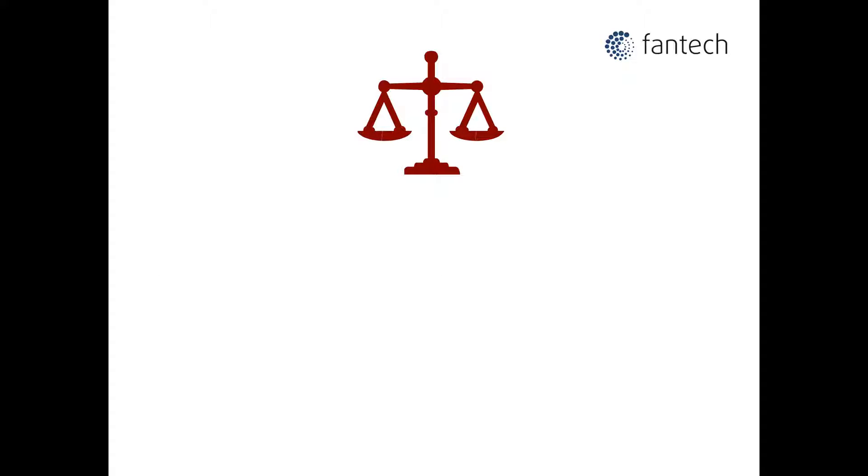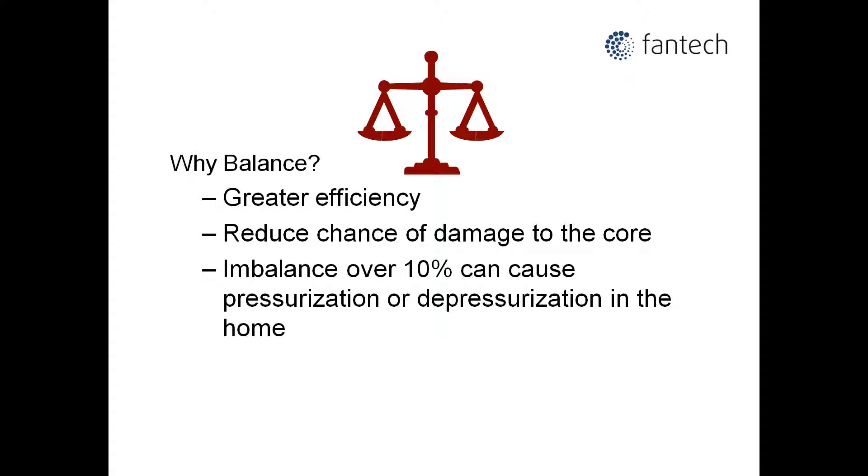A HRV or ERV works best and is most efficient when the air flows are equal. In areas where freezing occurs, a balanced system stands less chance of freezing up. Also it does not depressurize the home causing backdrafting of fossil fuel appliances or open fires, or pressurizing the home forcing moisture into the structure causing damage and possible mold growth.